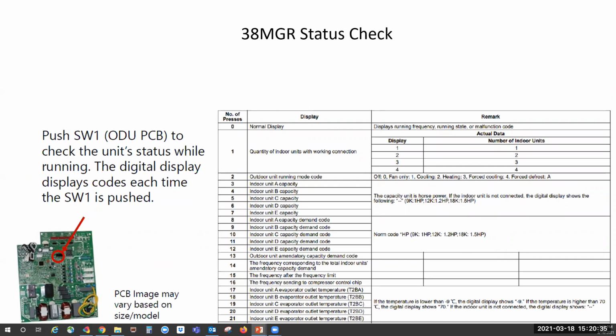On the 38 MGR, you go outside, you have a little SW1 button next to the display, and you push that once and it'll tell you indoor, how many indoor units you have, which ones are working. The second time you push it, it'll tell you what mode it's in, the number of capacity of the units. This is a good idea because this will tell you what your capacity of your unit is, because just because it's running doesn't mean it's running full, or if it's running half, or at a certain percentage. This will also tell you what your various sensors are doing.